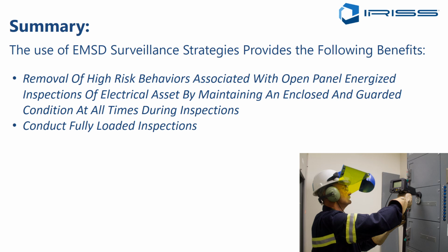We conduct fully loaded inspections in line with the requirements of NFPA 70B. We don't need load banks or anything—we're looking at the equipment at peak load times and actual operating conditions, which for an engineer is a far more valuable inspection to make.